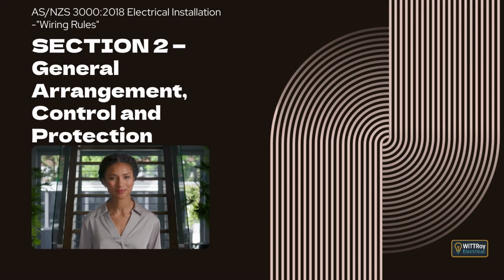Another situation is when the conductor is not in a location where opening the circuit would create a fire or explosion risk, and one of the following conditions is met. The first condition is that the conductor is on the load side of a change in capacity and is already protected by a device placed upstream. The second condition is that the conductor supplies equipment that cannot cause an overload, such as certain heating appliances. The conductor must also have no branches or socket outlets connected along the way. The third condition is when the conductor supplies equipment used only for telecommunications, signaling, or control, where overload currents cannot occur. Examples of these arrangements are shown in later figures of the standard.